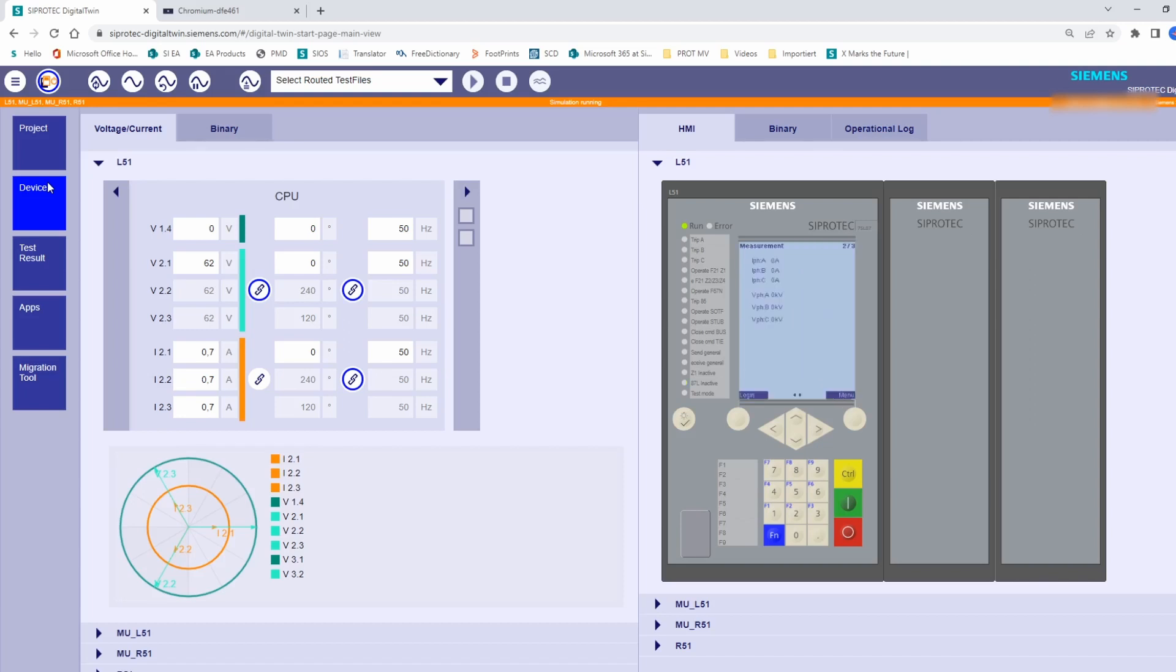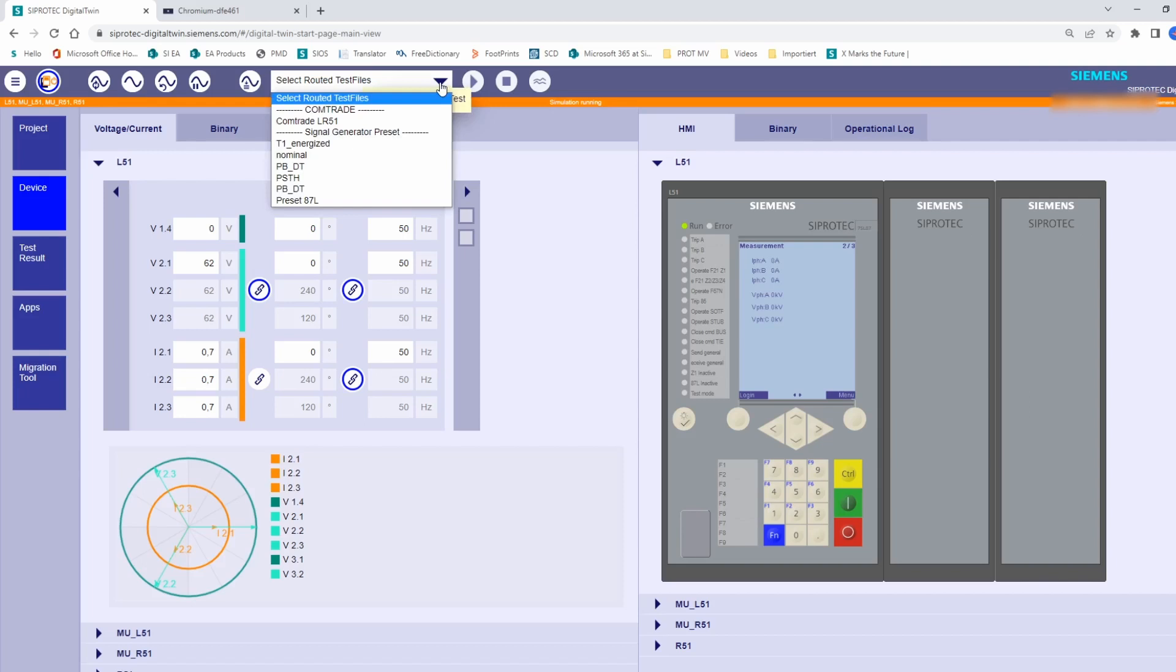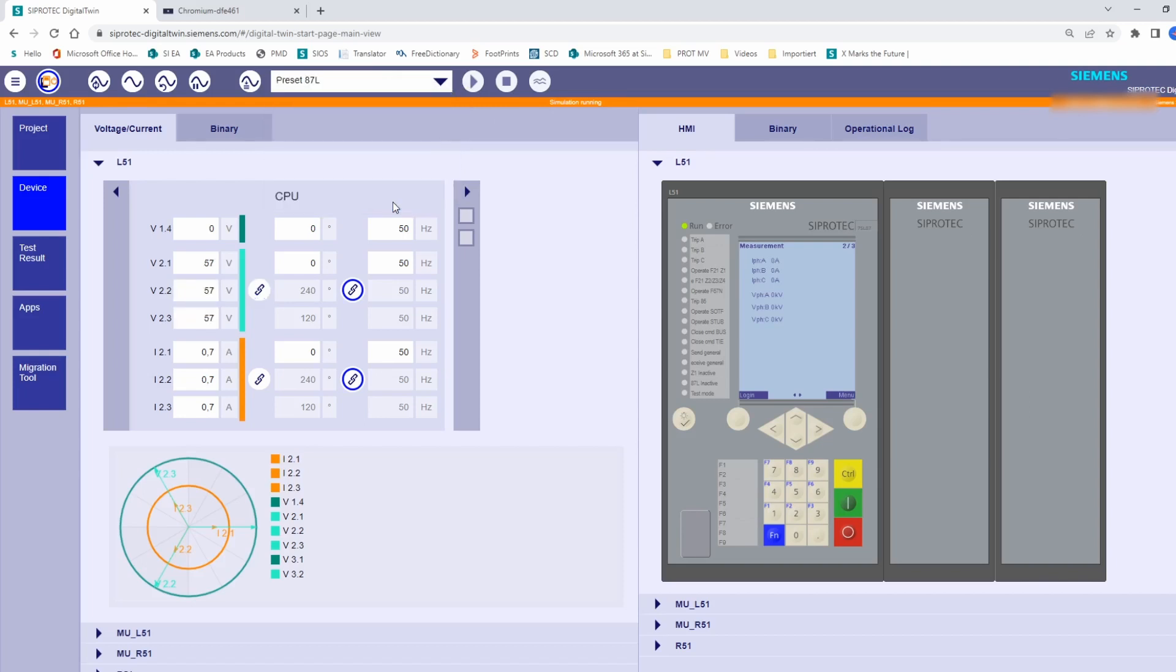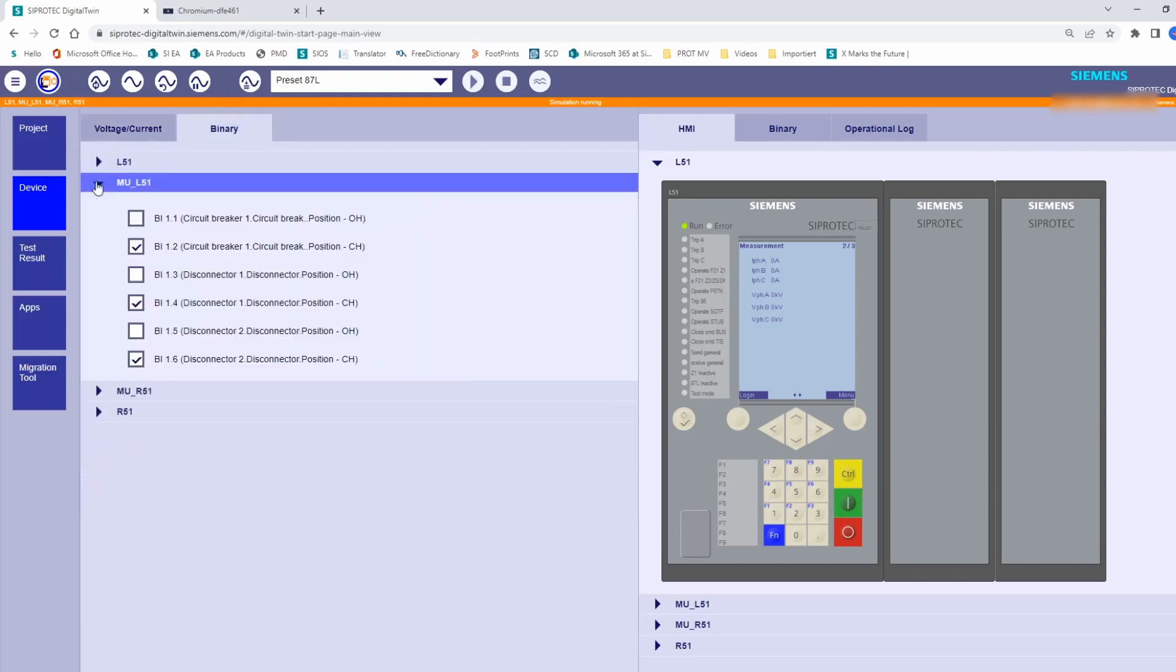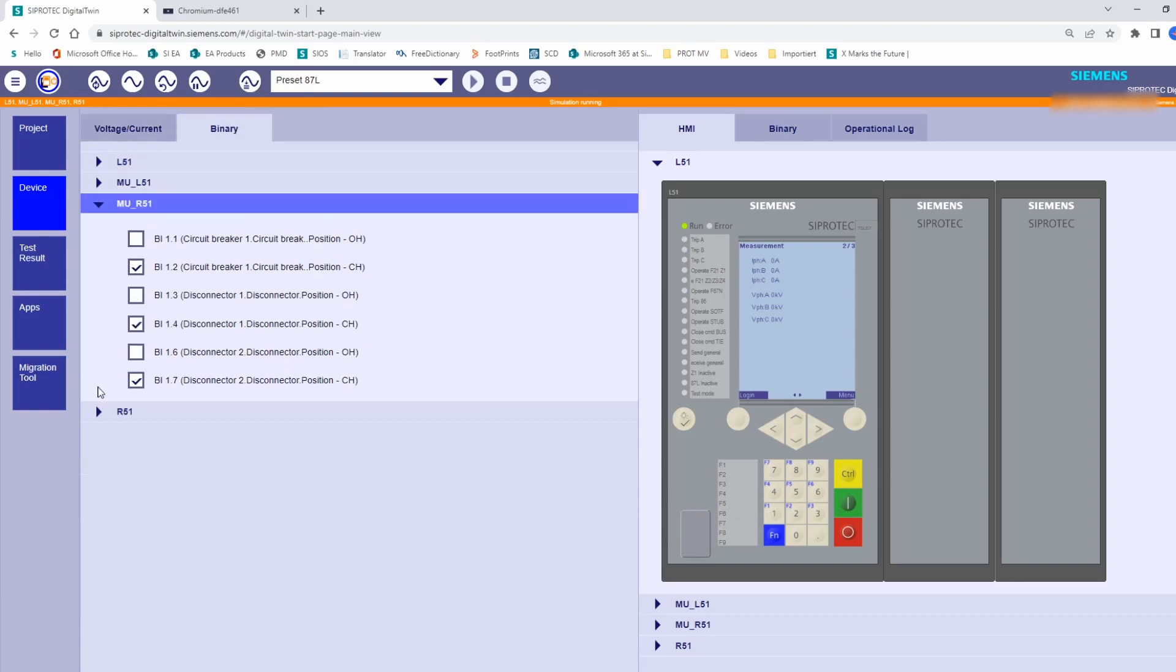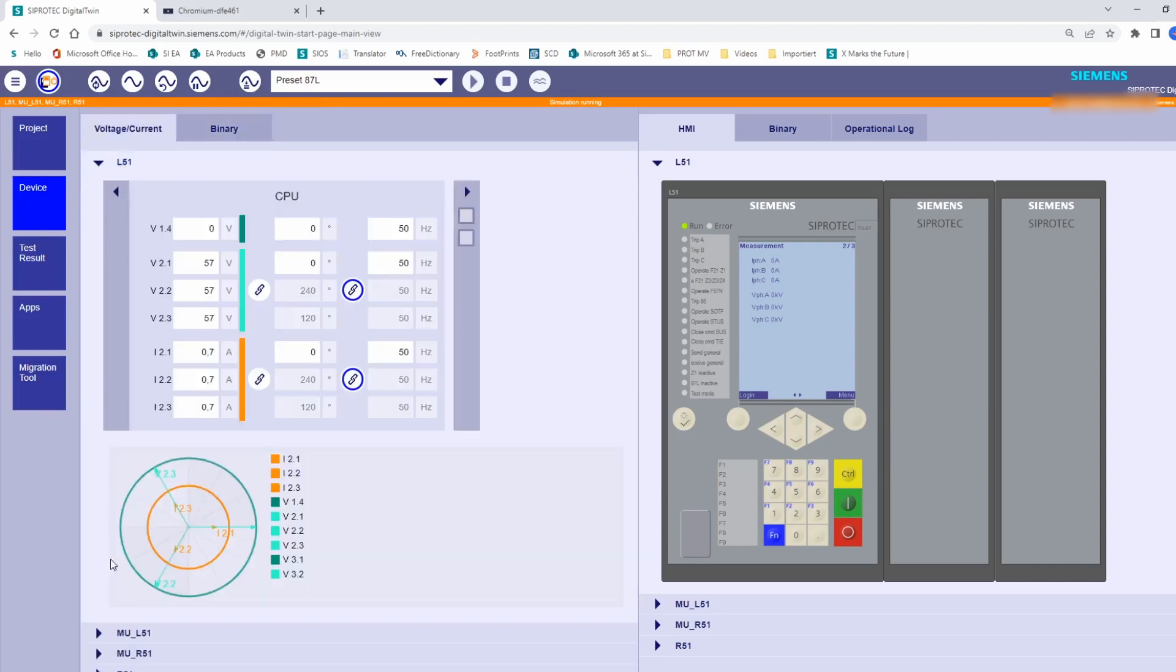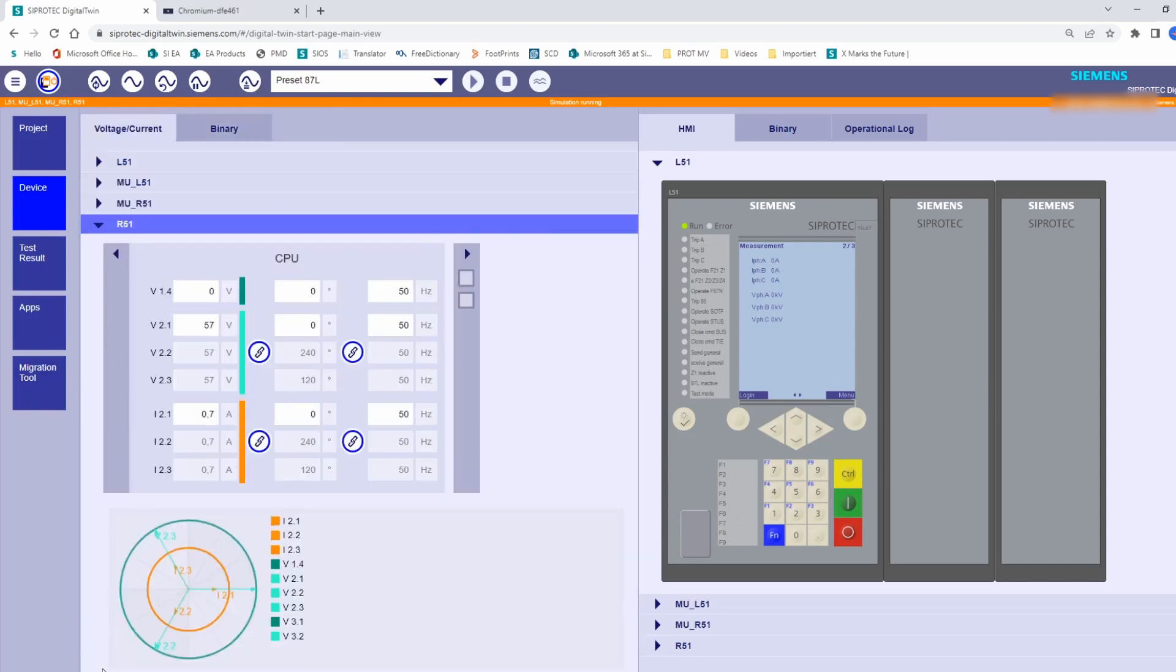So, we start with one static injection. Note that we can still do both, static injection and COMTRADE replay, and we can test the different positions of the switching devices. For the static injection, we can also use some preset values. In our preset 87L values, circuit breaker and disconnectors are closed, by forcing the corresponding binary inputs of the merging units. These values will be transmitted via GOOSE once we inject them, and the position will be shown in the graphic display of the protection devices.